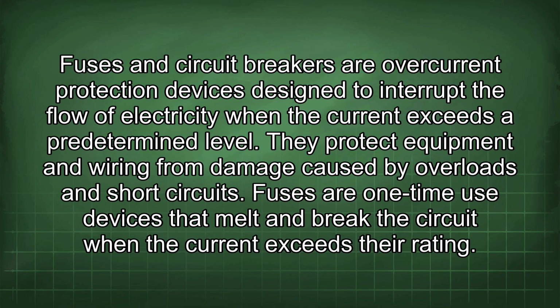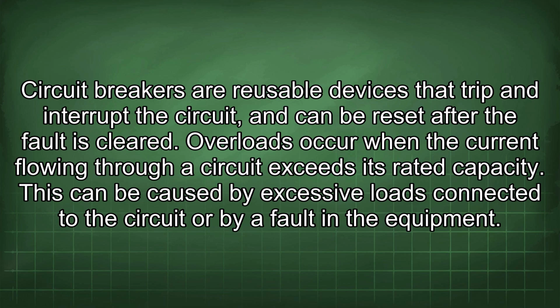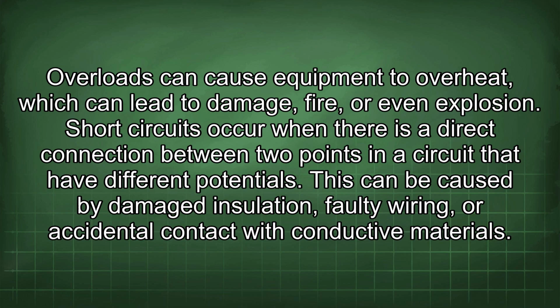Fuses and circuit breakers are overcurrent protection devices designed to interrupt the flow of electricity when the current exceeds a predetermined level. They protect equipment and wiring from damage caused by overloads and short circuits. Fuses are one-time use devices that melt and break the circuit when the current exceeds the rating. Circuit breakers are reusable devices that trip and interrupt the circuit and can be reset after the fault is cleared. Overloads occur when the current flowing through a circuit exceeds its rated capacity. This can be caused by excessive loads connected to the circuit or by a fault in the equipment. Overloads can cause equipment to overheat, which can lead to damage, fire, or even explosion.